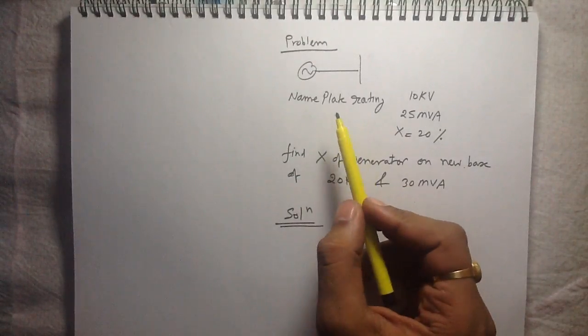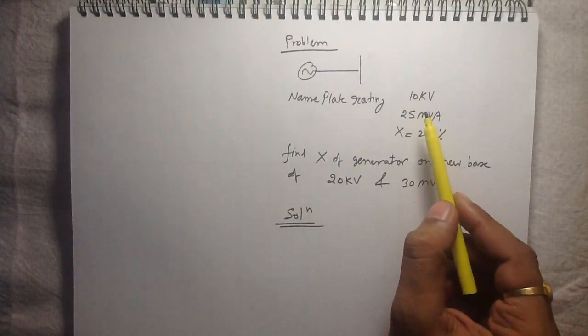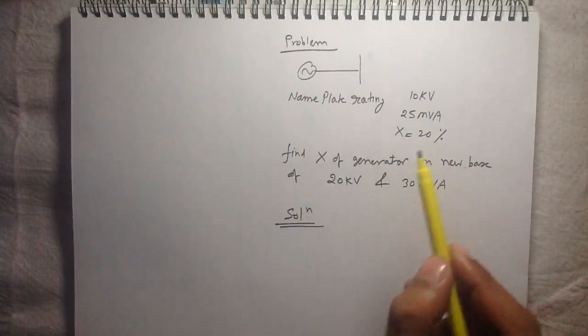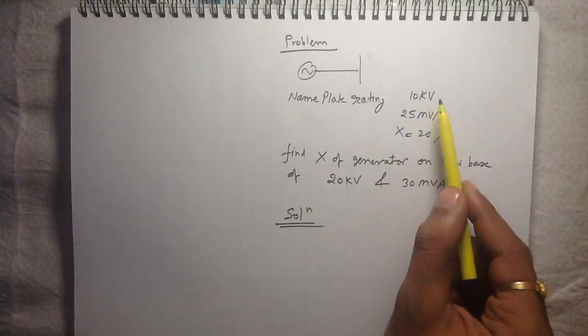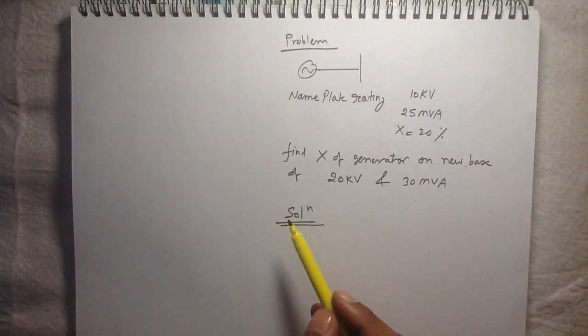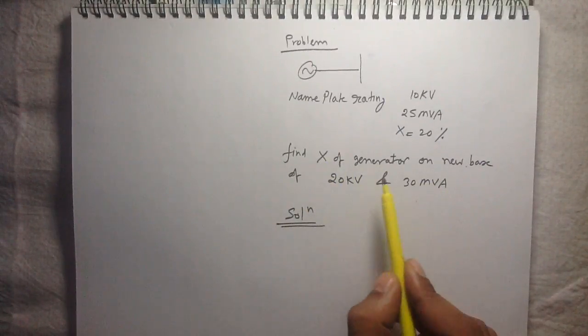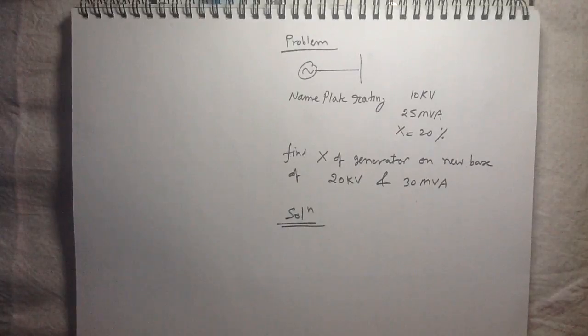In this problem, the nameplate rating of the synchronous generator is given as 10kV, 25MVA, and the reactance is 20% on these base values. We have to find out the reactance of the generator on a new base of 20kV and 30MVA.